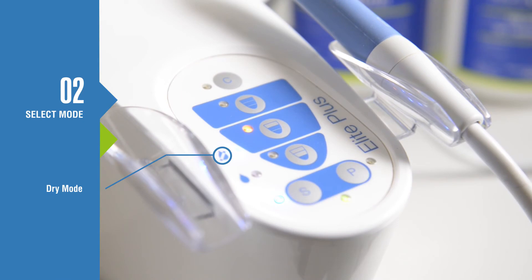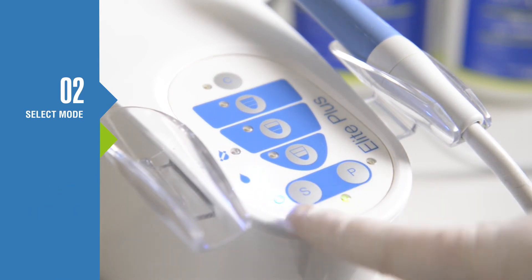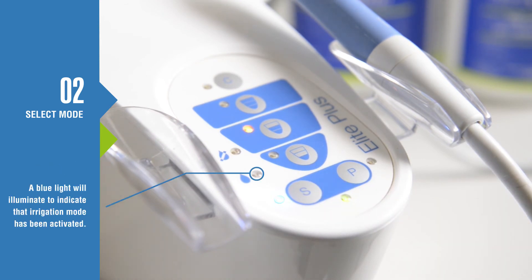Pressing S will toggle the dry mode, irrigation mode, and back to normal scaling mode. If there is no water coming from the scaler, check to see that you have the irrigation mode turned on.